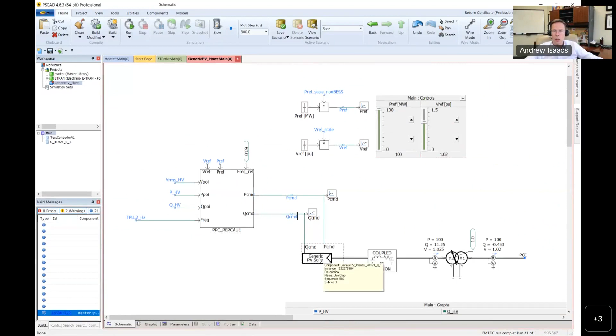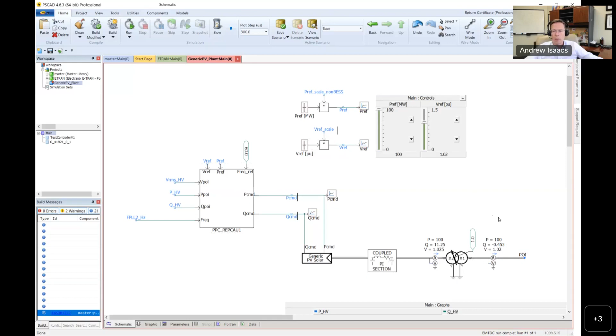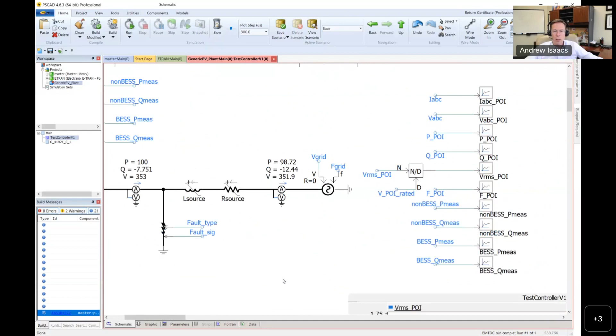All you do as a developer is take this file and add your equipment. In this case, I'm using a generic power plant controller and a generic solar plant, with the transformer up to the POI, plus a collector system up to the POI, and drop it in here. You set the power rating, and the rest of this is an automated test controller. You can enter some basic parameters about the plant, and the rest is stuff you shouldn't really have to change—it all comes with it. Inside the test controller there's more detail, but the electrical piece is the part I want to show you.